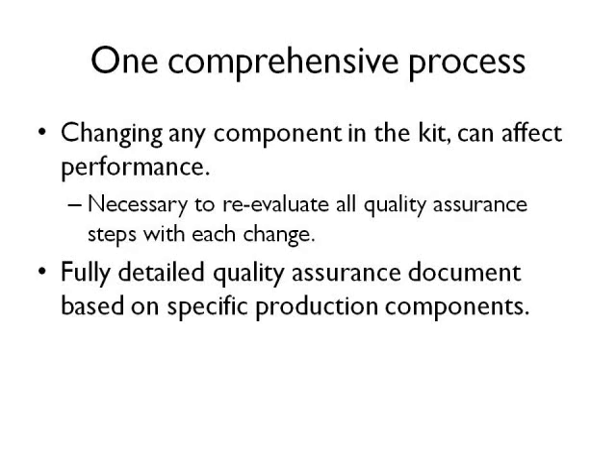Every component of a diagnostic application has the potential to affect performance. If you change anything at all — generally because you have negotiated a lower price for a given component — the performance of the entire system needs to be re-evaluated. Throughout this process, it is necessary to work towards a fully documented production system, with specific quality control tolerances for each step. This is not a trivial exercise. The key is to work through this process with maximum efficiency so that you can bring your product to market sooner while minimizing failures.